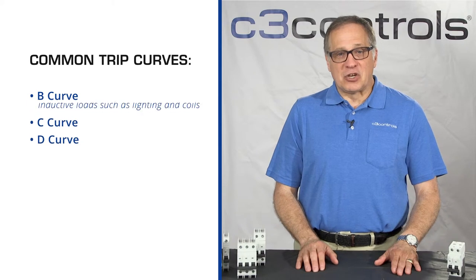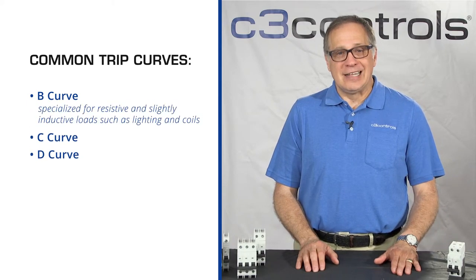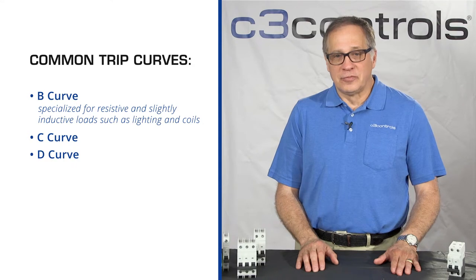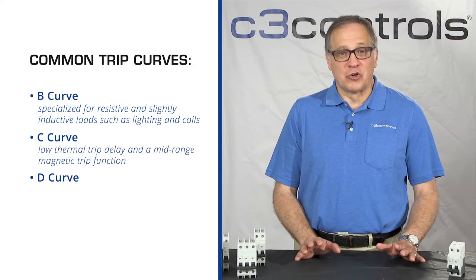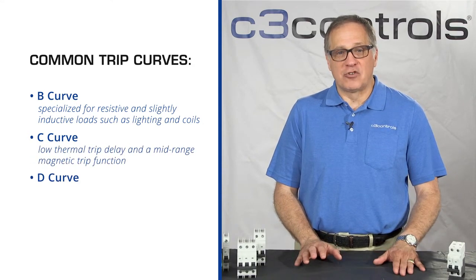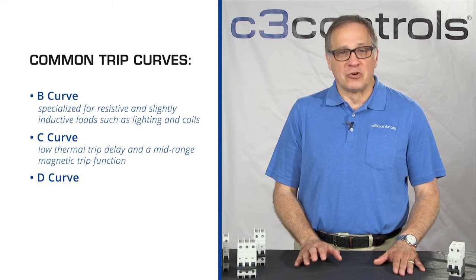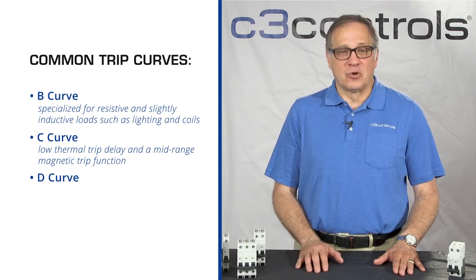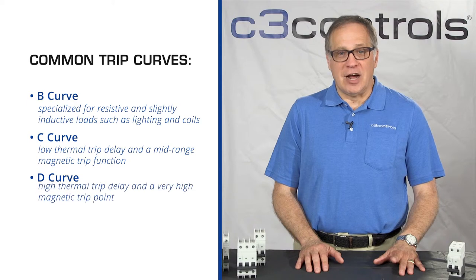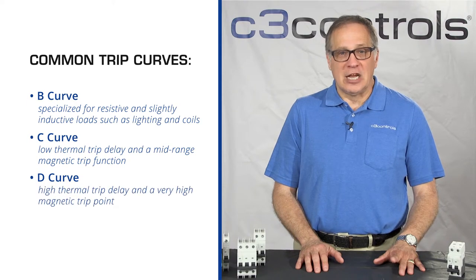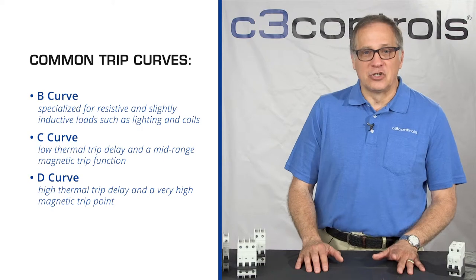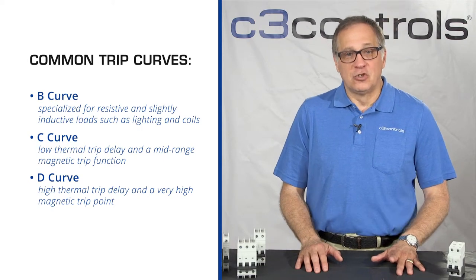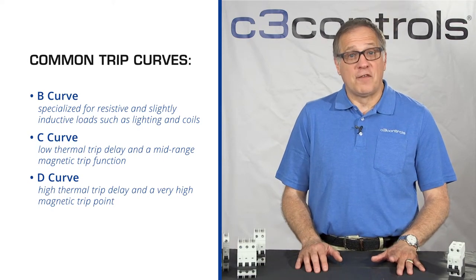B curves are specialized for resistive and slightly inductive loads such as lighting and coils. C curves have a low thermal trip delay and a mid-range magnetic trip function to protect against low inrush current motors, resistive loads, and control circuits. D curves have a high thermal trip delay and a very high magnetic trip point to protect high inrush current motors, heaters, transformers, and inductive loads while preventing a false trip.